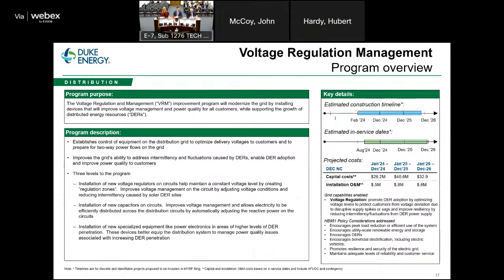Now to the closely related voltage management program. This part of our effort is about damping out the voltage fluctuations from the intermittency of DERs once we've applied that control. The planning engineers leverage the CYME toolset to perform voltage and power analysis on each circuit. They first do the integrated volt/var control analysis to make sure we've got that capability, then immediately do a sequential study to look at any potential voltage regulation and management equipment needed based on the expected penetration of DERs.